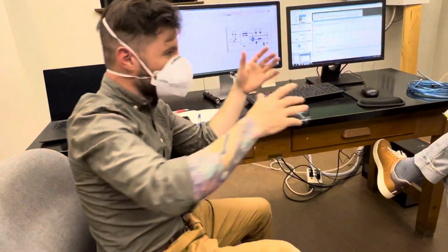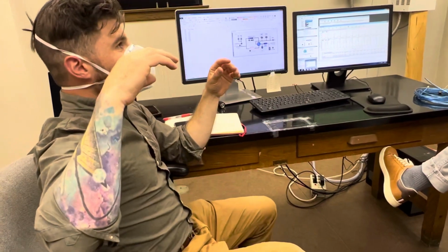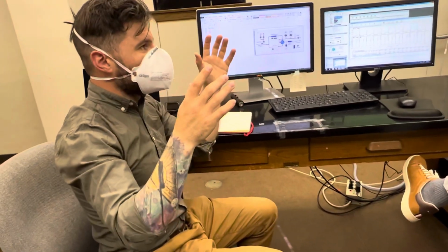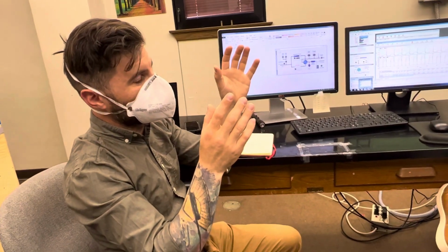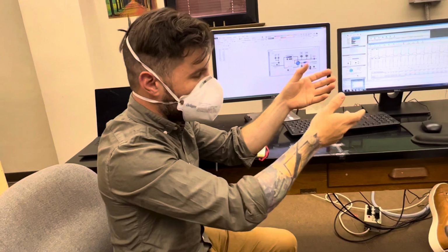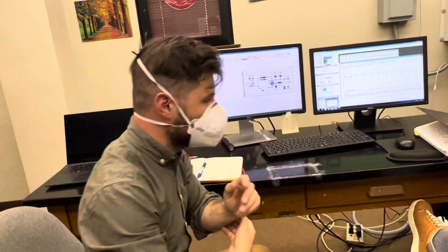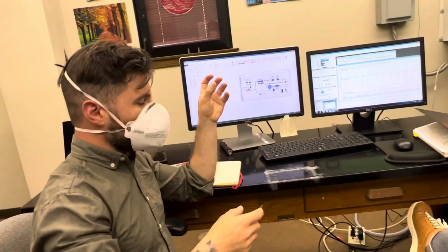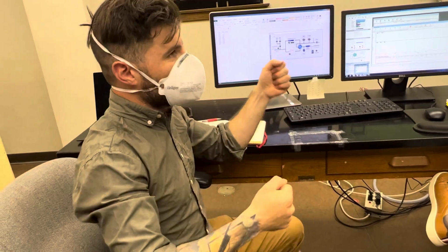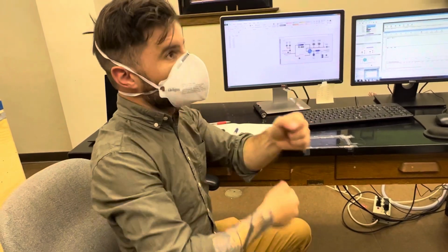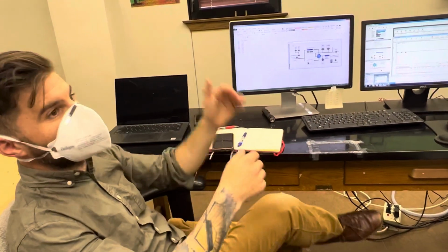It's easier to see when the source is out, but there's 2 magnets that give everything a spin, and because everything's being ionized, you have a statistical probability of what becomes ionized, what gets trapped in the trap, and what actually comes through the source to be collected by the Faraday cups. The H3 factor shows you how much of the false signal is getting through. It's always going to happen, but it shows you the amount, and you want it to be below 10.